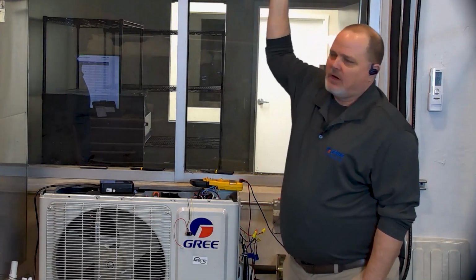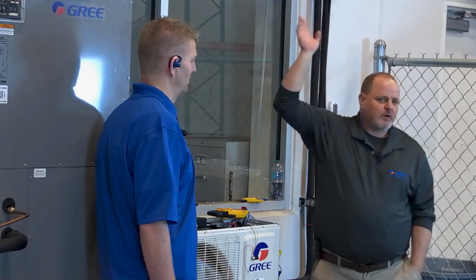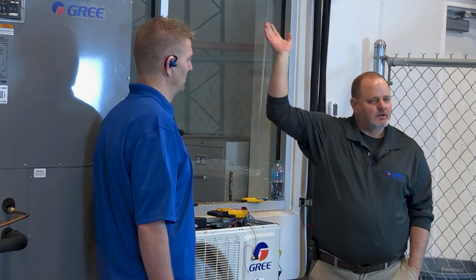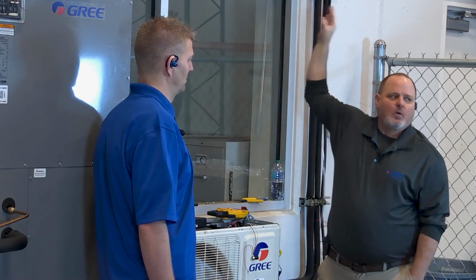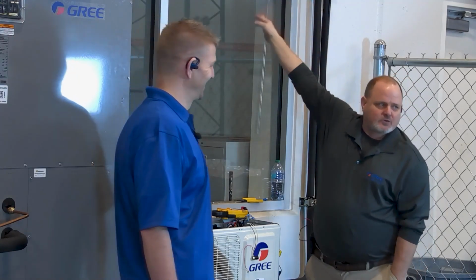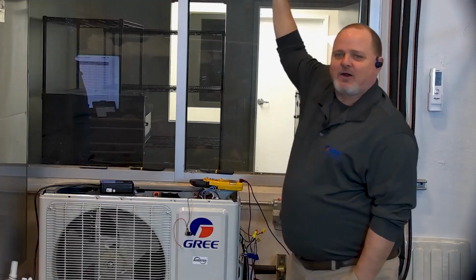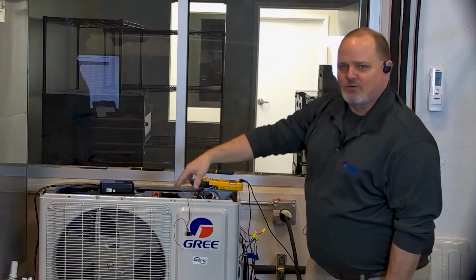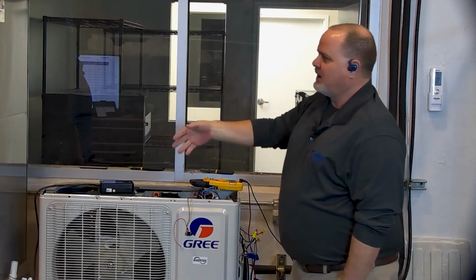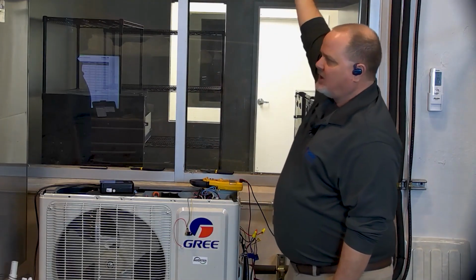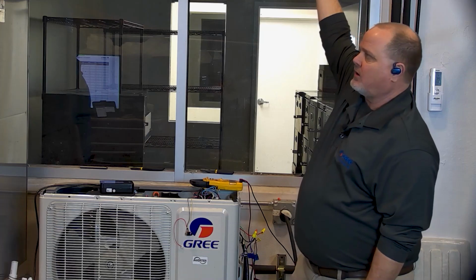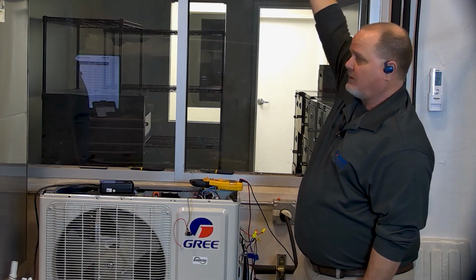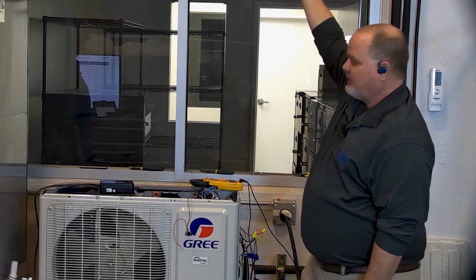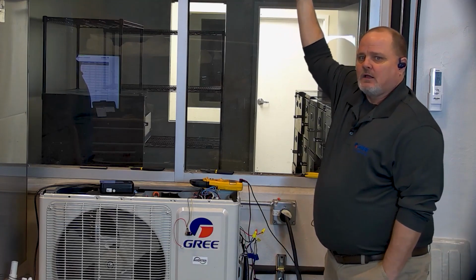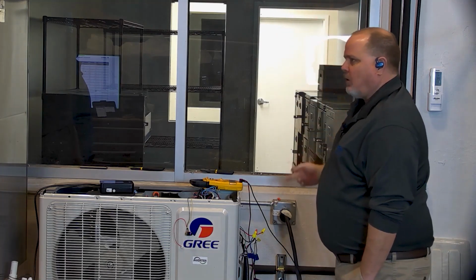And I'm going to say it because there's going to be one person out there that says, well, you didn't tell me to do that. You need to kill the power while you hook up those 3 wires and then turn the power back on and then use the service tool to simulate the outdoor unit. If it does simulate the outdoor unit and that indoor unit will run, then you know for a fact something is wrong with that wire.